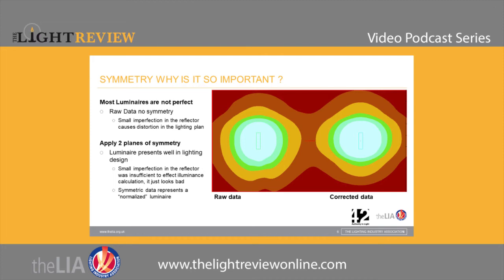It's easy to take that data and correct it. We average each quadrant of the luminaire so they're all equal — the 0–90°, 90–180°, 180–270°, and 270–360° azimuth quadrants are averaged to produce one typical quadrant, reproduced four times to show a perfectly symmetrical file. That perfect symmetry never actually exists, but it's what the designer needs in his design software to show the client the effect, because when you put 20 luminaires in a room it's the average effect of all 20 that you want, unbiased by any particular fault.